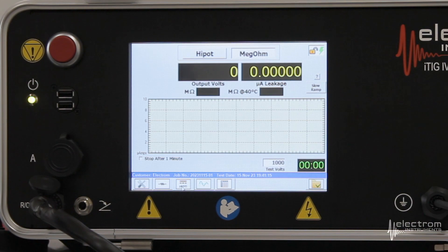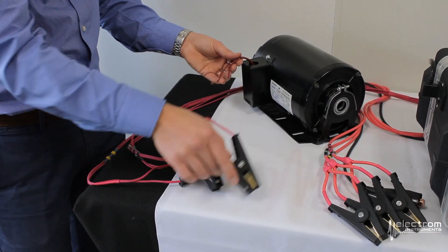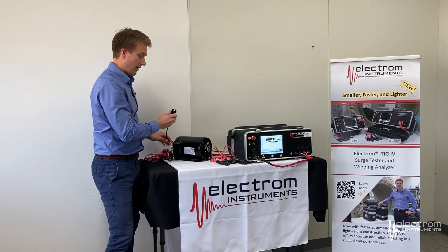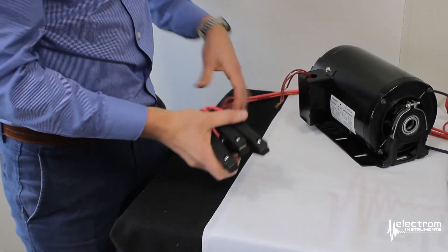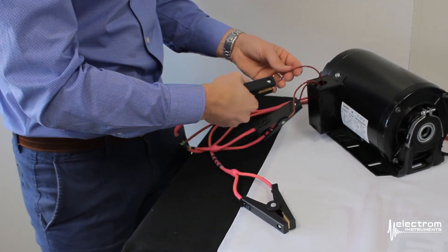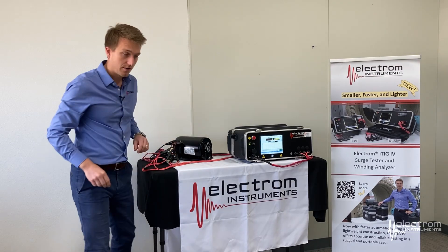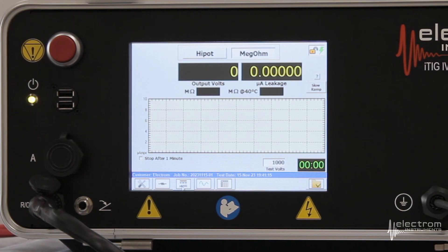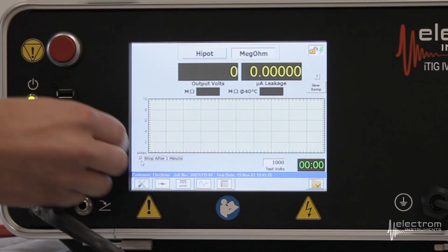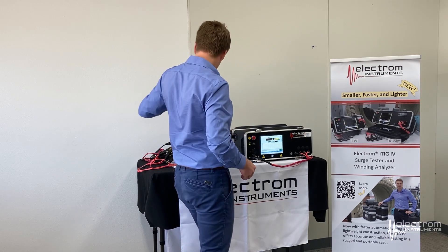Next up is the megaohm measurement. We disconnect the low voltage lead set and connect the high voltage lead set. First, the ground lead — very important to connect for this measurement, otherwise you won't get any leakage current — then leads one, two, and three to phases one, two, and three. Now that the leads are connected and nobody is touching the motor, we are safe to start the test. We have a couple of features to cover: one is the Stop After One Minute option, which I'm going to check. That means the test set will automatically shut off after one minute.